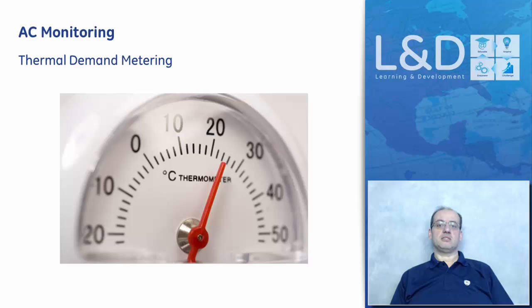Non-operational data is picked up by an engineer and used later for further analysis of the state, overall status, like we said in the AC monitoring, right? You're taking the max and the min and the RMS and the sags and the swells over a period of time, and you go, well, you know what? Maybe my power factor is not perfect in here, and maybe I can achieve a better power factor. So this is what AC monitoring is all about, to achieve a lot of non-operational data that will help you over time to take decisions. Nevertheless, some of the data is still instantaneous.